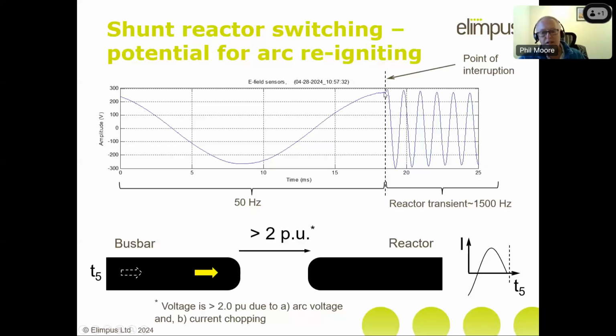So all the capacitance associated with that shunt reactor, the capacitance in the windings or the bushings or the bus bars connecting it to the circuit breaker will all be charged up to system voltage, and probably a little bit higher because you've got the arc voltage to add on to that as well. And as soon as the arc goes out, that voltage then starts to resonate with the inductance in the reactor, and it resonates at a frequency of about 1500 Hertz, maybe 1500 to 2000 Hertz. It just varies on the different sort of applications.